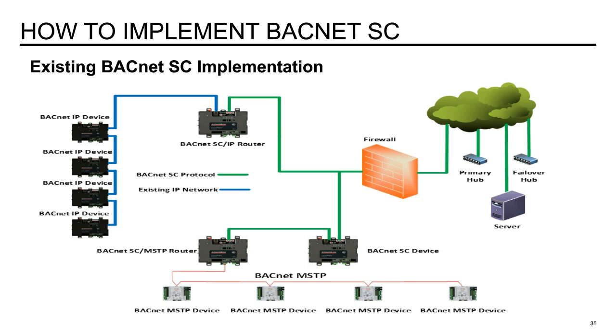The buffering is typically a function of the switch or the controller, so it's not really a function of BACnet SC. The protocol itself won't buffer any data. That's going to happen at your switch level or the controller level. So I hope that answers your question.